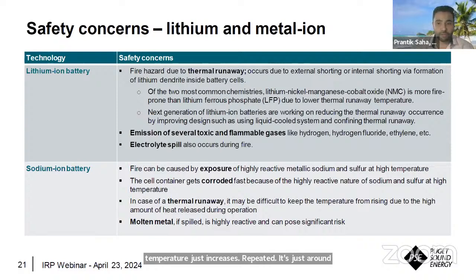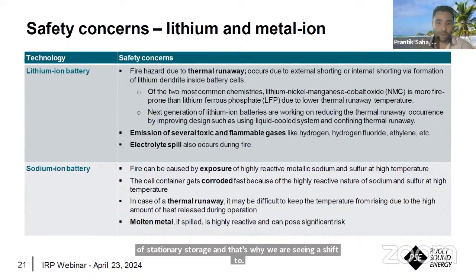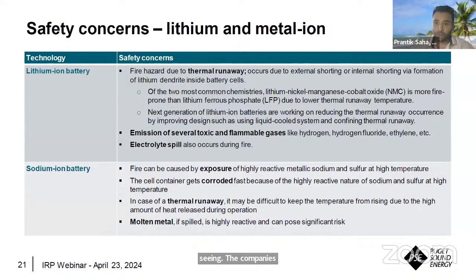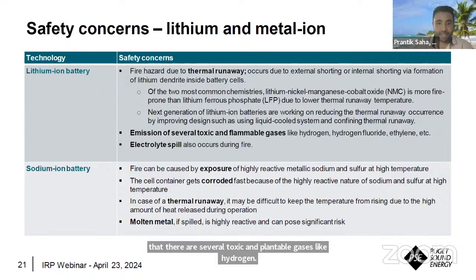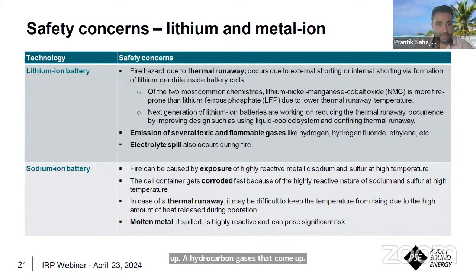We have seen some fire occurrences due to thermal runaway in lithium-ion batteries. One thing to note is that LFP chemistry is definitely way less risky than NMC chemistry for stationary storage, and that's why we're seeing a shift to LFP chemistry for stationary storage applications. We're also seeing companies deploying liquid-cooled systems to prevent thermal runaway, because it's more efficient than air-cooled systems. However, if fire occurs, we see toxic and flammable gases like hydrogen fluoride, ethylene, and other organic hydrocarbon gases released, and electrolyte spill can also occur. So that's about the lithium-ion battery.